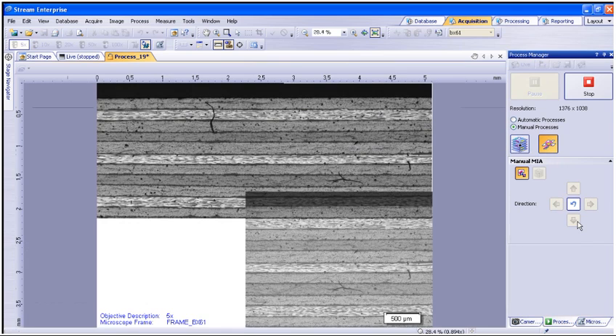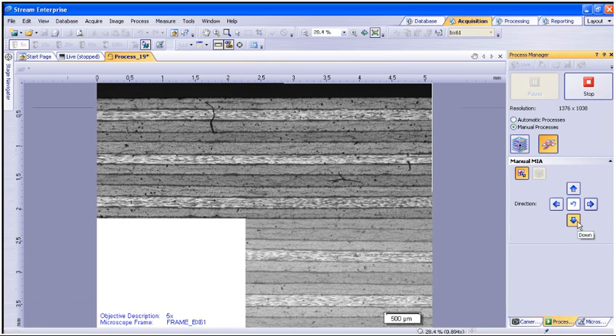This will now generate the overlap and watermark image below the second captured frame. You will have to manually adjust the stage to align this next frame.